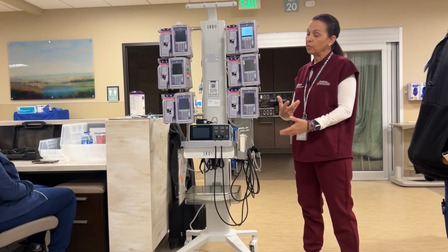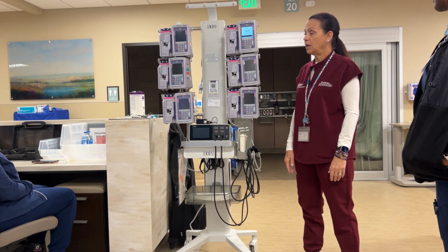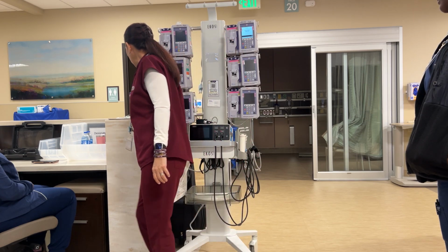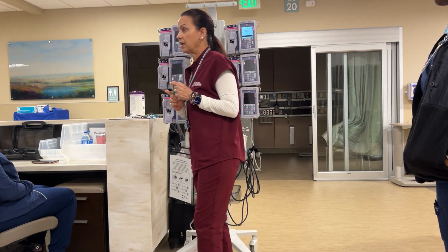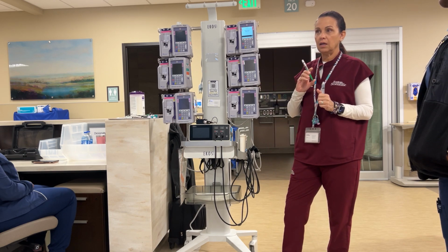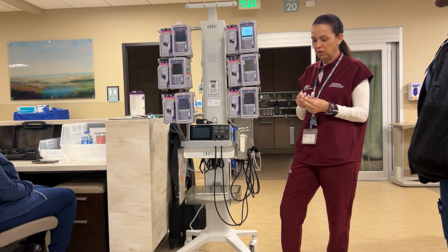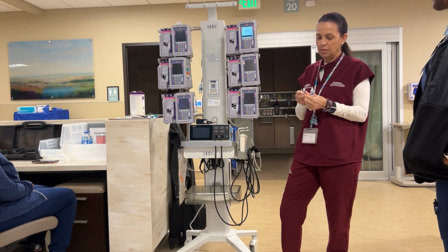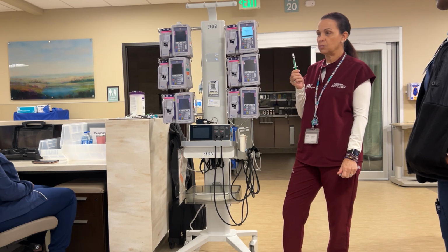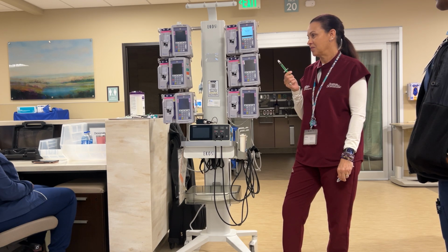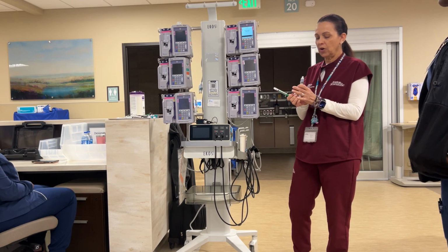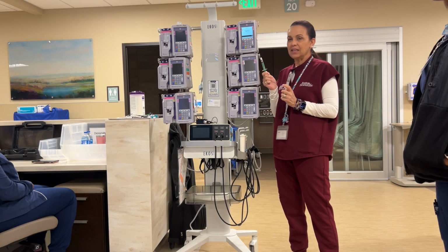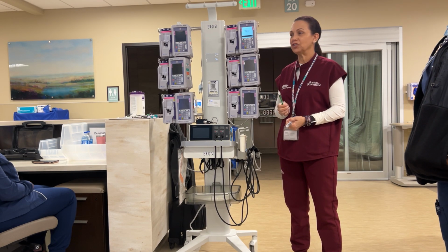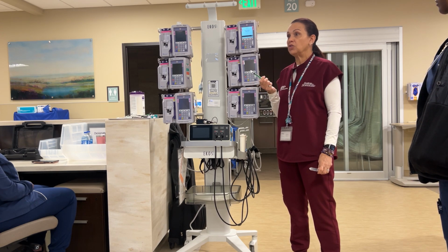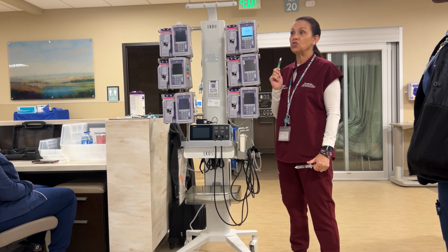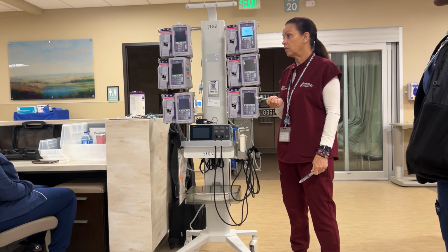We might have you do a forward flush. If you do, it's normally with a 3 cc syringe, not a 10. This is going to be easier. The entire priming volume for the drug lumen, all 3 lumens, is 0.8 ml. So super tiny. So when you go in with like this versus this, it's just going to be such a hard push. So it's easier with the 3. We don't use a 1 cc syringe. That's too much PSI, and we've actually had the lumens rupture.